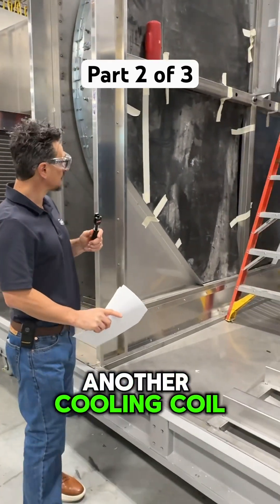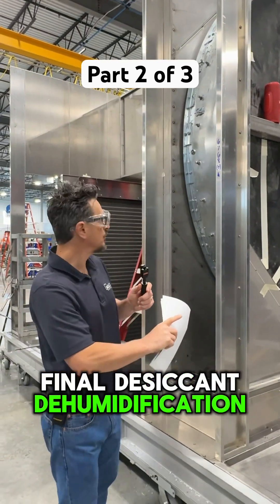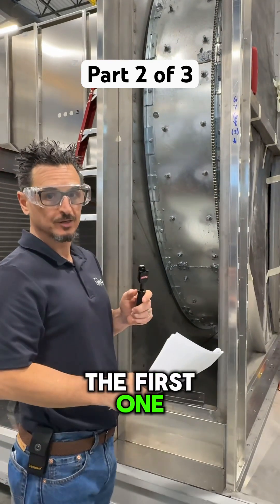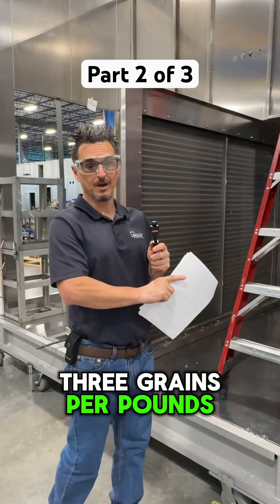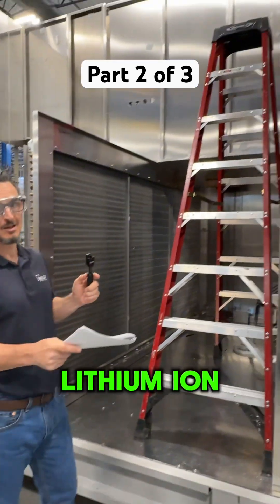We go through another cooling coil, and this is the final desiccant dehumidification of this unit. This one's a lot deeper than the first one because this is where we're really pulling it down, and it's leaving here at 3 grains per pound of dry air — extremely, extremely dry. This is for a lithium ion application.